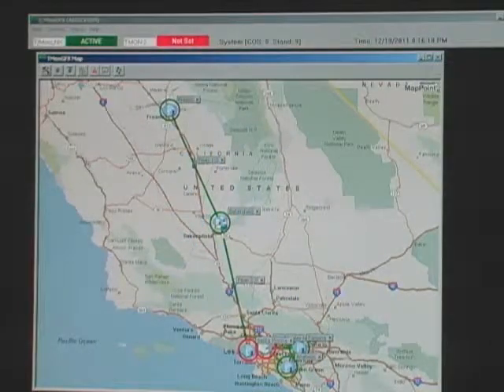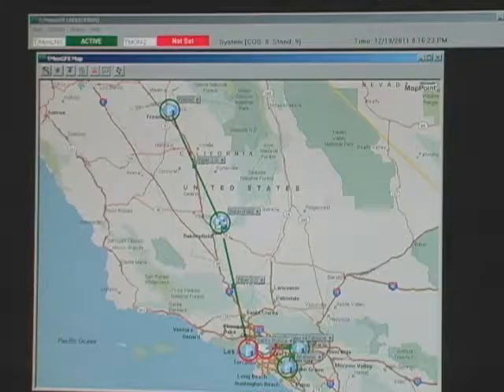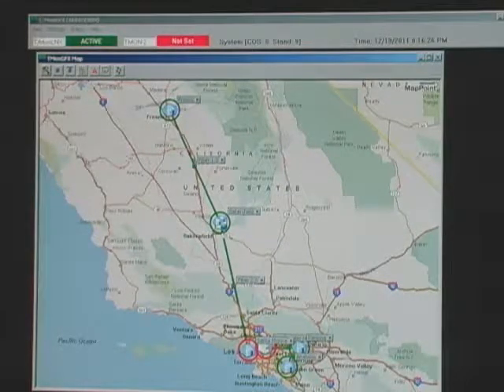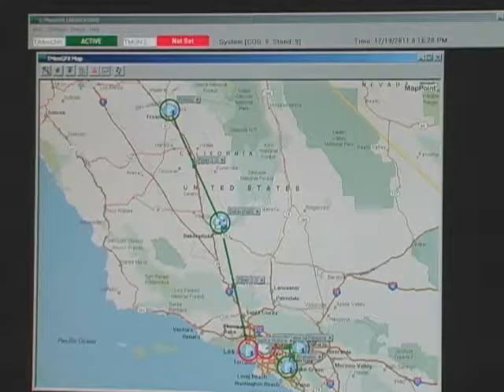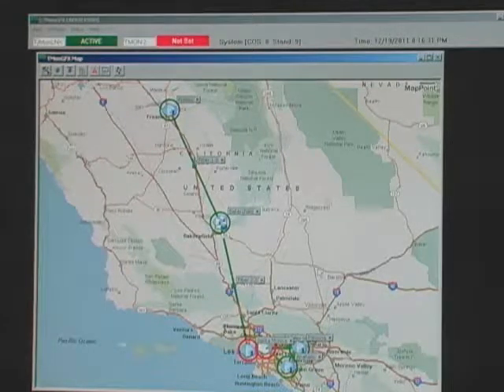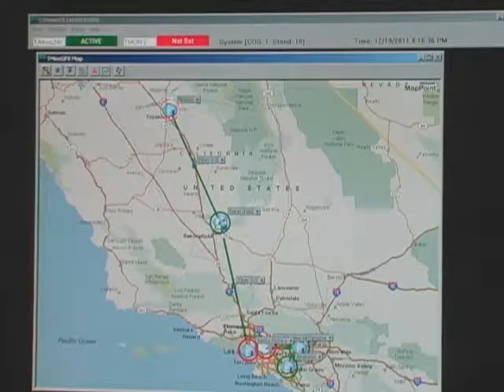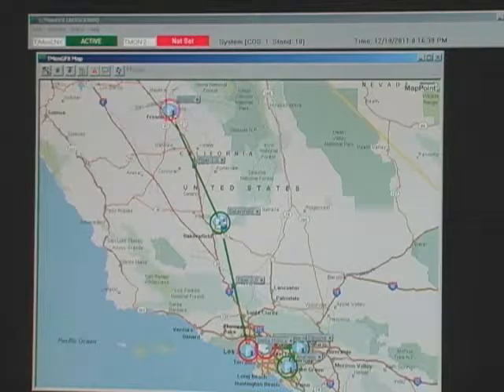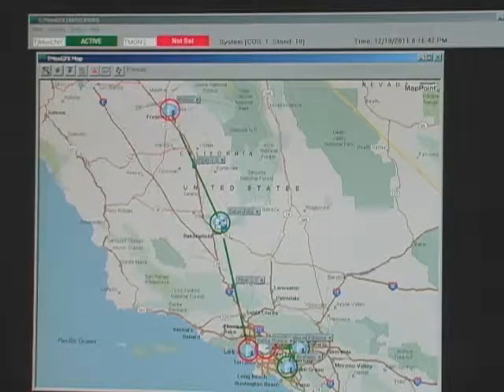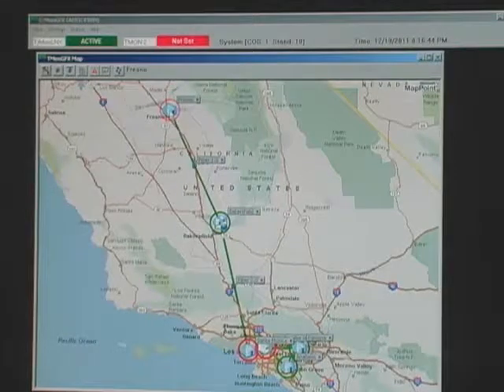This is the T-Mon GFX geographic map interface. You'll see in this example network that I have a regional network from Fresno down to Los Angeles. So let's bring in a simulated alarm, and we'll take a look at the process of drilling down through the interface to get all the necessary details to identify and then correct that alarm condition. We can see here the Fresno site had started blinking red, indicating a new change of state and a critical alarm, so we better drill down into that site.